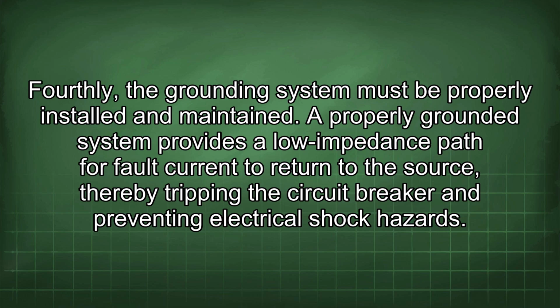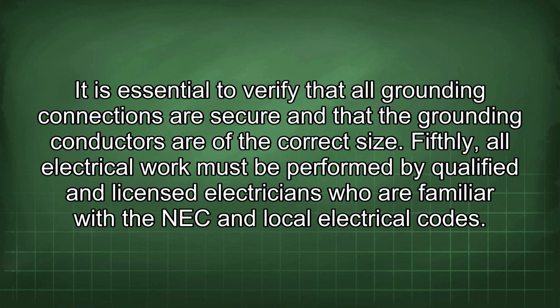Fourthly, the grounding system must be properly installed and maintained. A properly grounded system provides a low impedance path for fault current to return to the source, thereby tripping the circuit breaker and preventing electrical shock hazards. It is essential to verify that all grounding connections are secure and that the grounding conductors are of the correct size.